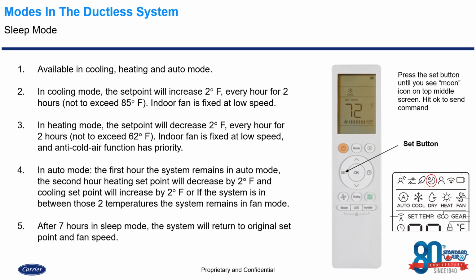Okay, and then finally, after 7 hours in sleep mode, the system will return to its original set point and fan speed. Now, I will advise you, this is something that I do not recommend that your customers do, depending on their comfort level. As you can obviously tell, as I went through the different explanations of how the system is controlled in this particular mode, if the space is getting up to 85 degrees or going down to 62 degrees, you're going to have an uncomfortable temperature at home, especially if there is somebody in the home when they activate this, hence if they would go to sleep or if they would leave for vacation.